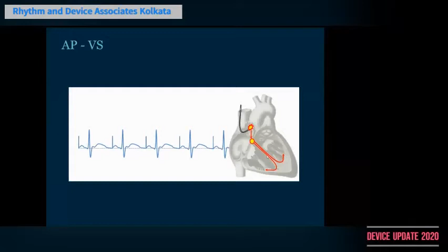So DDD timing. Suppose there is an atrial paced event. After an atrial pacing spike is given, one thing that you have to remember is that a refractory period is also started in the ventricular chamber. So for a few milliseconds, say 40 or 50 milliseconds, the ventricular chamber is also blanked out for any events occurring. This is to prevent crosstalk.